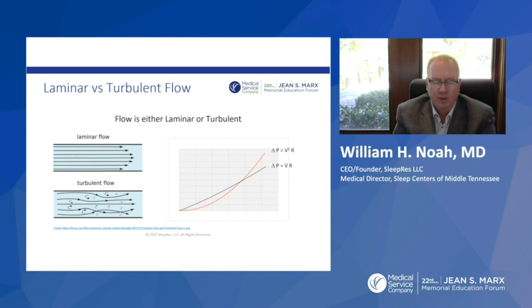Talking about resistance—the slide is missing something at the top that got lost when it was transferred over, but in the circuit, everything that's encountered is a resistor. That's what's missing from the top of my slide: everything's a resistor. The fan itself is a resistor. As the fan spins and translates electrical energy into kinetic energy, it generates pressure on the fan blade, which begins the flow. It's going to encounter the flow meter in the machine, which hangs down into the air path, creating resistance. Then it goes through the humidifier, which doesn't generate much resistance.